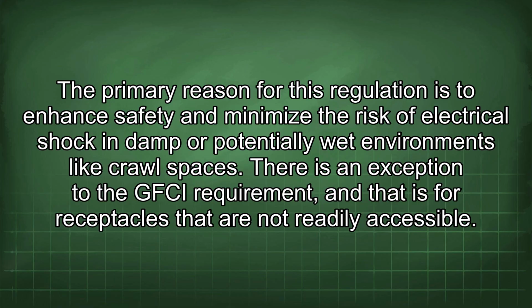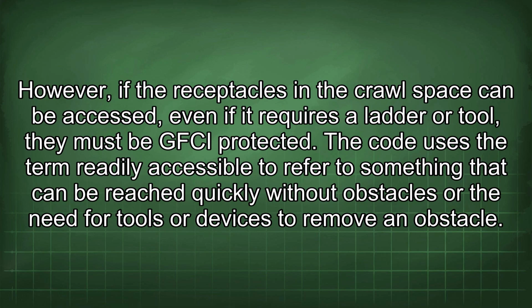There is an exception to the GFCI requirement, and that is for receptacles that are not readily accessible. However, if the receptacles in the crawl space can be accessed, even if it requires a ladder or tool, they must be GFCI protected. The code uses the term readily accessible to refer to something that can be reached quickly without obstacles or the need for tools or devices to remove an obstacle.